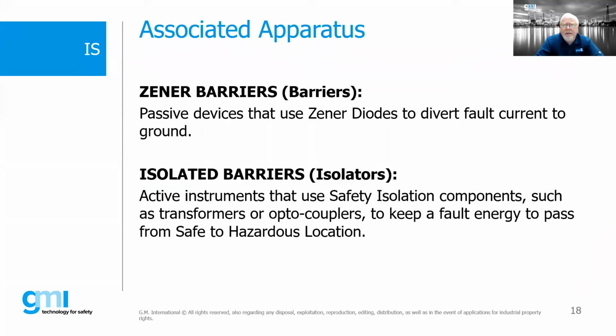There are two different kinds of associated apparatus commonly used in the marketplace. I wouldn't say the most common, but the original was the Zener barrier, and we'd typically call those barriers. That was the first intrinsic safety design. IS was developed many years ago in the mining industry, where it was used for protection of signaling devices in the mines. Zener barriers are passive devices, and they basically don't switch on, if you will, until we have a fault condition. The Zener diodes open up and divert any of that excess energy to ground. It's very important that we have a good ground.